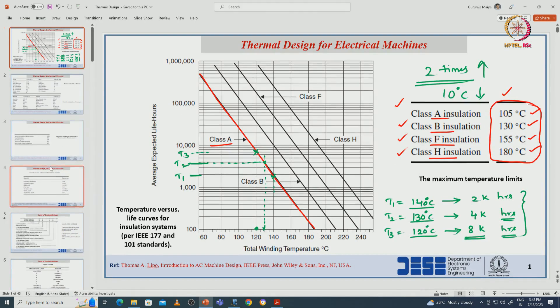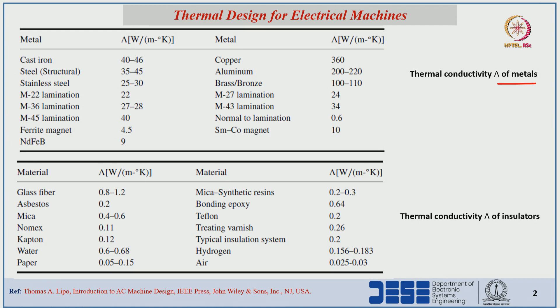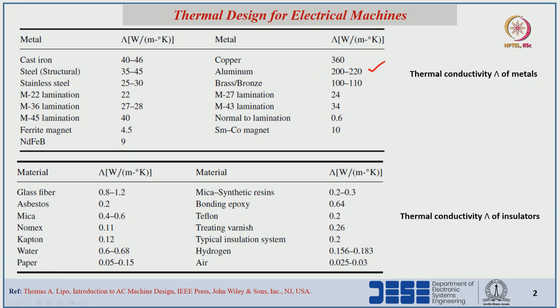We can see different thermal conductivity values for materials used in electrical machines. For copper, thermal conductivity is 360 watt per meter Kelvin. For aluminum it is 200 to 220. For M27 and M43 laminations, the values are 24 and 34 watt per meter Kelvin respectively. For stainless steel, cast iron, ferrite magnets, and neodymium magnets, different thermal conductivity values are listed. Generally, copper windings are 360 and aluminum windings are 220 watt per meter Kelvin.